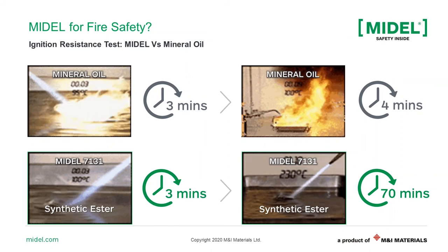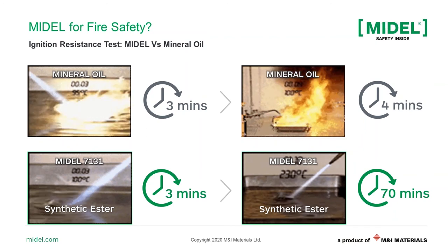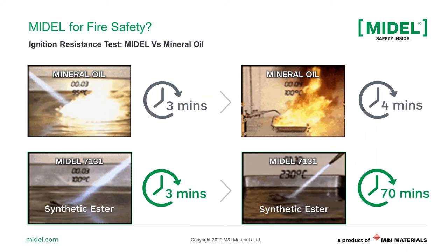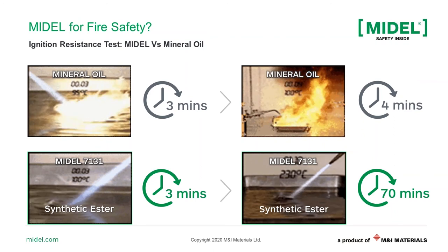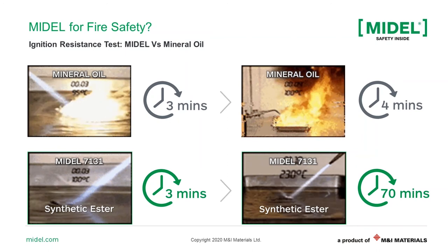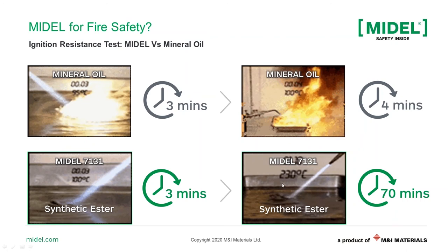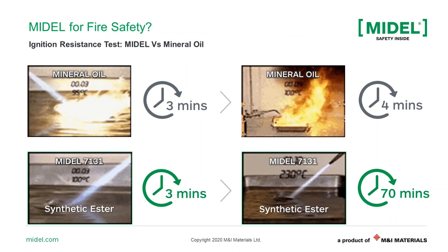In the case of Midel 7131, after three minutes we can see the bath temperature of the liquid is around 100 degrees C, which is a little bit higher than mineral oil — that is due to the better thermal conductivity of the ester. After 70 minutes, the bath temperature is around 230 degrees C, which is below its flash point and fire point. The torch is just blowing the surface of the liquid. The time is much, much longer than 70 minutes, compared to four minutes for mineral oil. In practical life, this gives you much longer time — for example, for evacuation of a building or a mine.